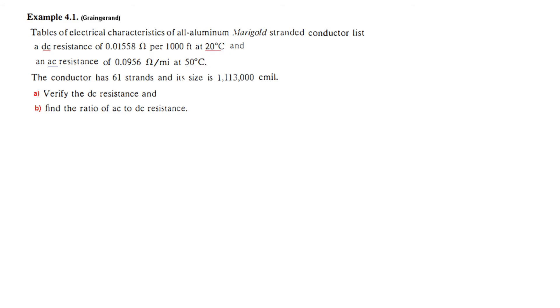Now let's do example 4.1. The tables of electrical characteristics of aluminium marigold stranded conductor list a DC resistance of 0.01558 Ω per 1000 ft at 20°C and an AC resistance of 0.0956 Ω/mile at 50°C. The conductor has 61 strands and its cmil area is 1,113,000 cmil. We have to verify the DC resistance and find the ratio of AC to DC resistance.